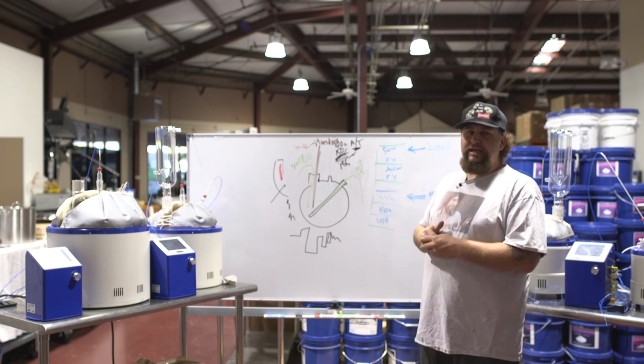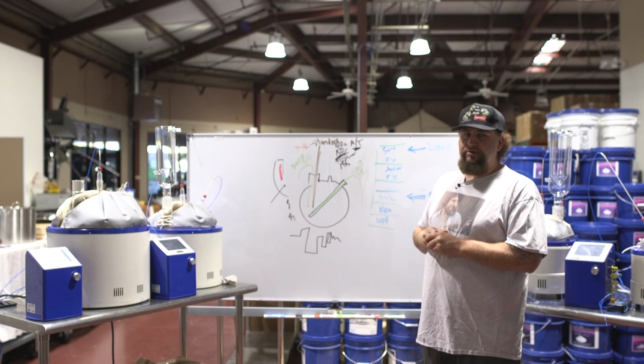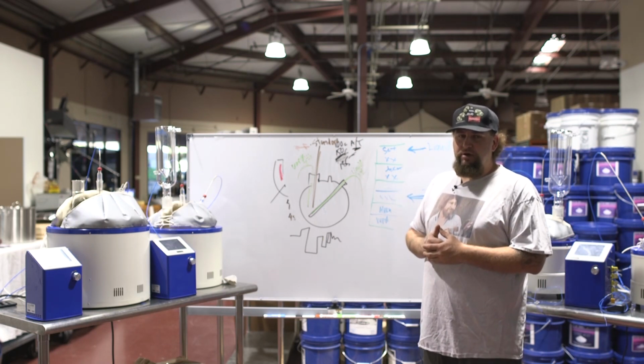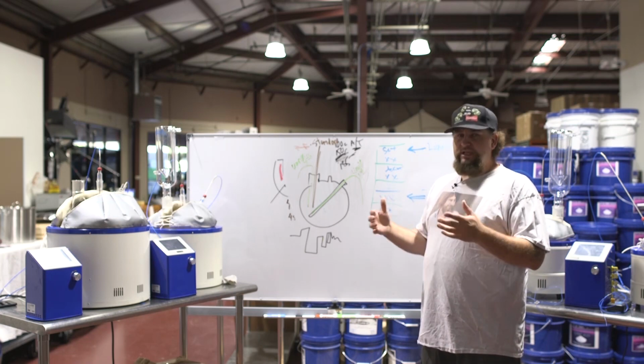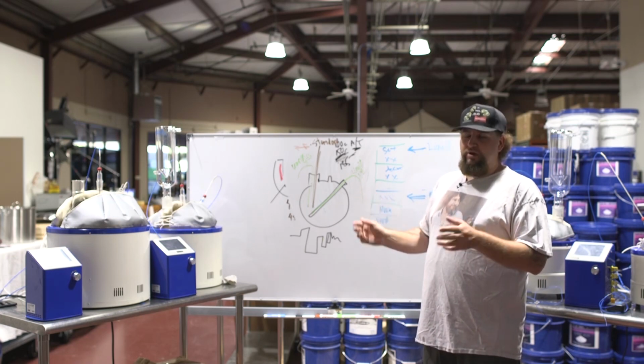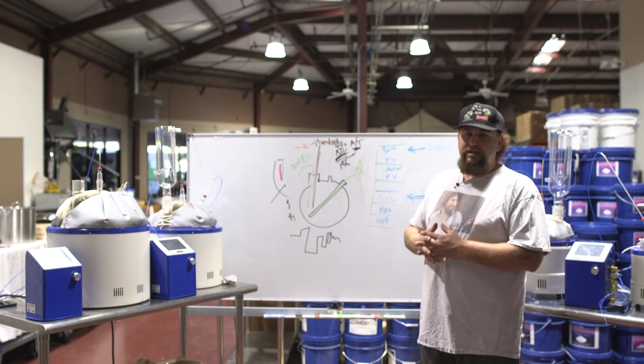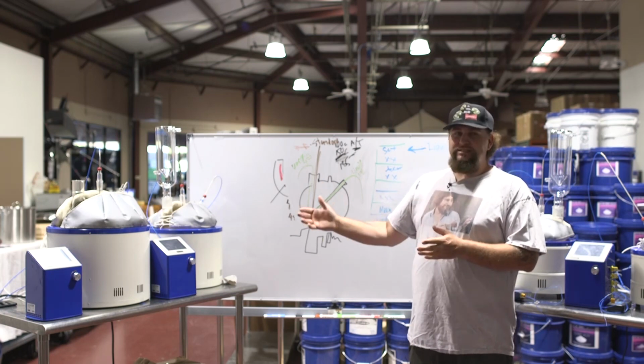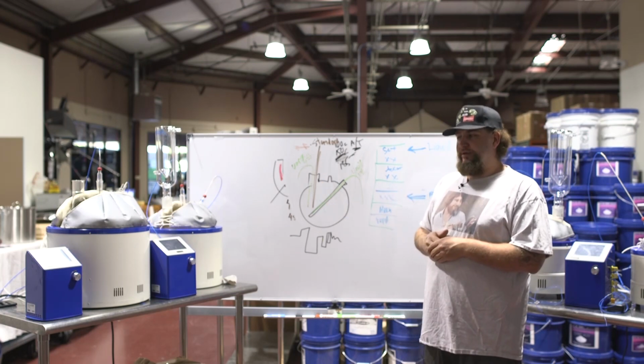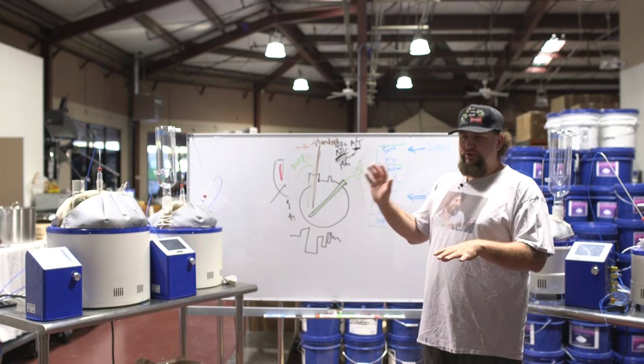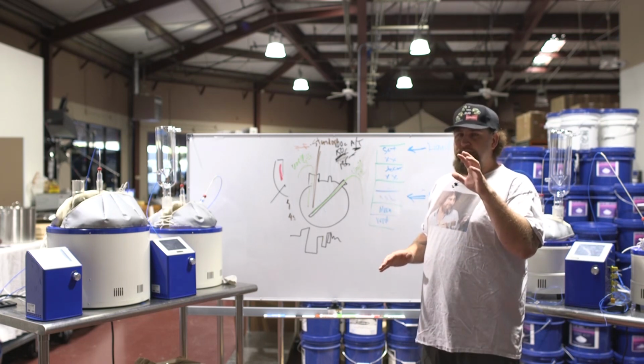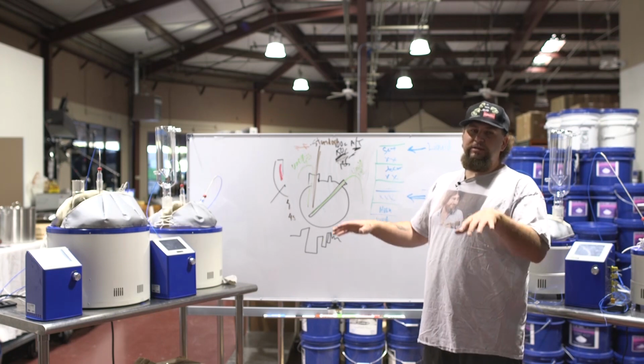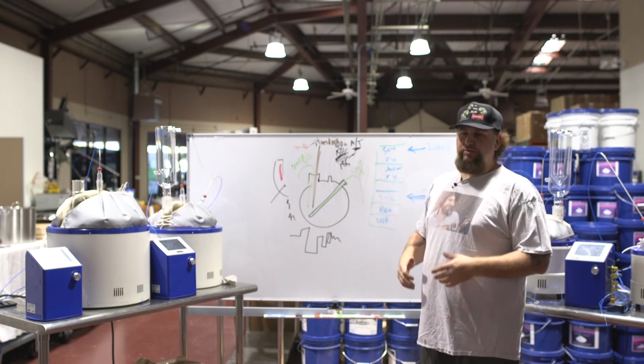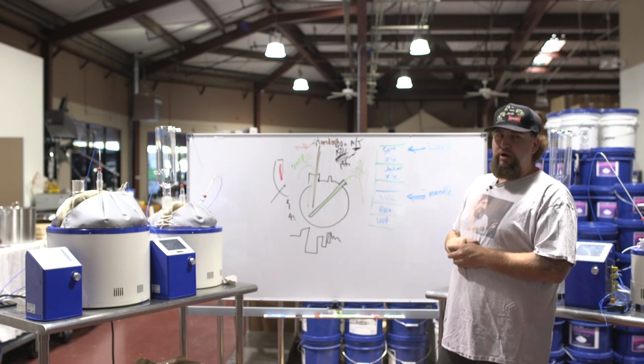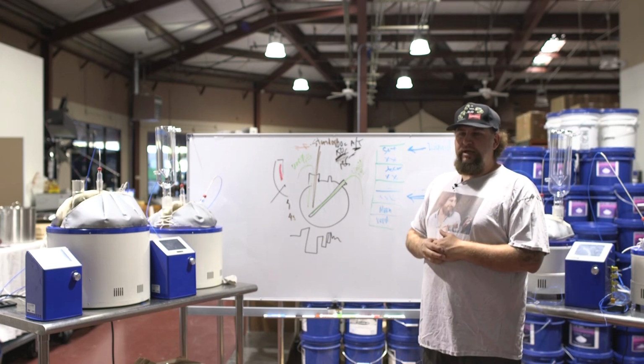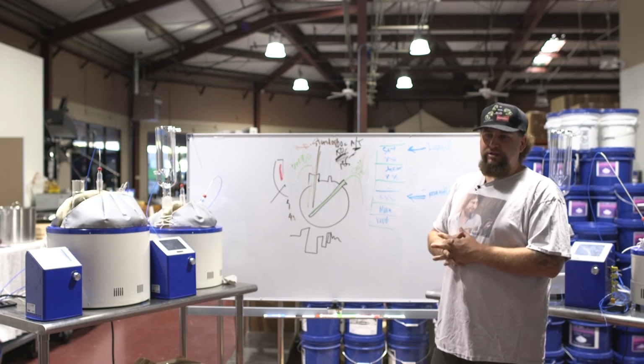These are our test and certified stations, so when you purchase a mantle from us, usually you'll get a call from me or someone on the staff, and we'll discuss this process with you just briefly overall, and we'll then do an in-house calibration and make sure it runs against a standard that we know. So when we're done with the calibration, we can go up in temperature and watch both units, your unit that you purchased and a bench test unit that's been calibrated, go up and at least meet at the same point, so we know that we're sending you out a top-notch product, that we're not just blindly sending you a mantle and expecting you guys to do the calibration, which is fine.